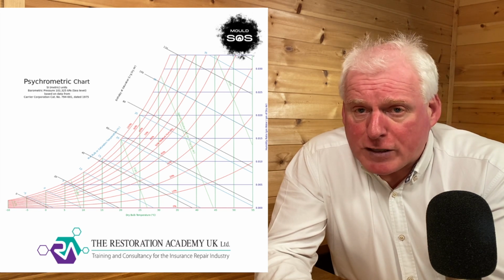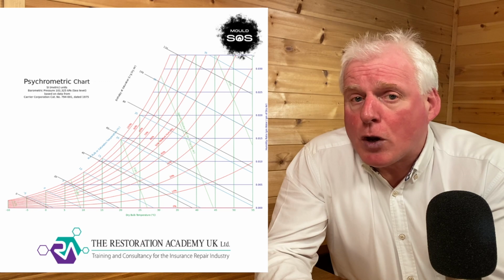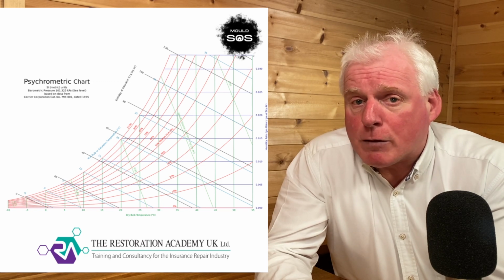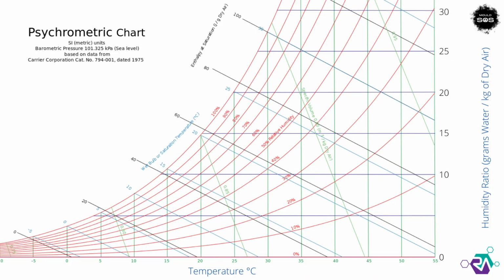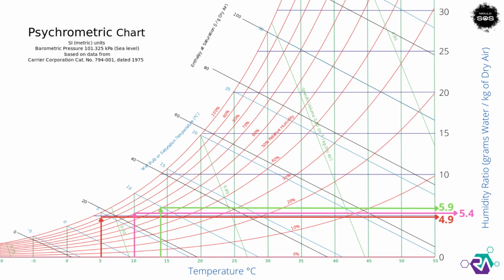For the purposes of this video, we are going to use humidity ratio, which is expressed in grams per kilogram in the metric world. Okay, so let's run the numbers. 90% at 5 centigrade gives us 4.9 grams of water per kilogram of air. Now let's not worry about the grams per kilogram bit just yet. Let's just compare the numbers. 70% at 10 gives us 5.4. 60% at 14 gives us 5.9. 50% at 20 gives us 7.3. 35% at 27 gives us 7.8.